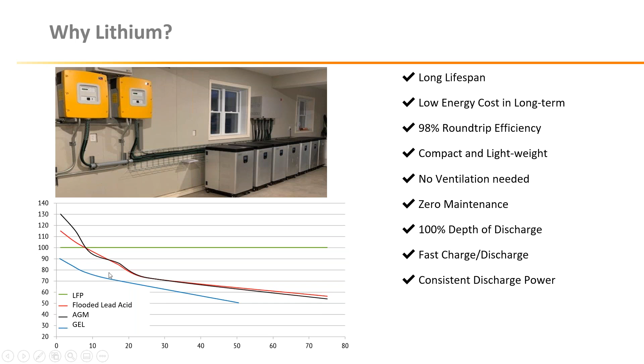So I'm going to go over a quick performance comparison of the LFP versus the lead acid system. So just went over this one here. So this was the discharge amps and then capacity that I mentioned. LFP is also less affected by temperature. So LFP has a very broad discharging temperature.